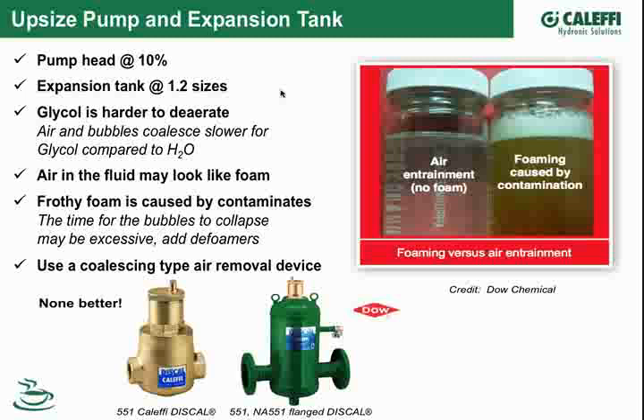No, you're exactly right. The air release properties of glycols are very different than water, and it comes back to the viscosity difference. Propylene glycol is going to be even slower air release than ethylene glycol, and of course water is ideal, a very rapid air release compared to glycol. So it's just a function of the physical property of the glycol, namely the viscosity.